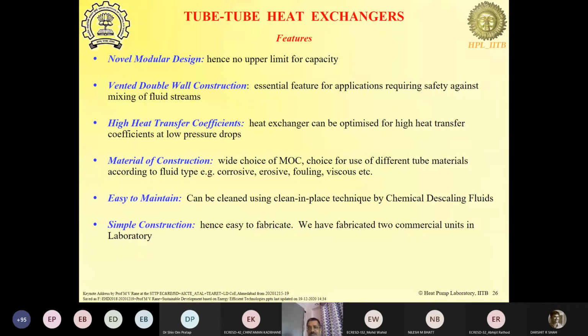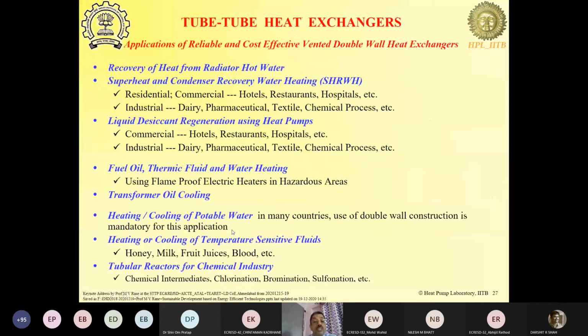So the cost of the heat exchanger can be much lower than the traditional alternatives, without compromising the compactness or safety or inventory of the heat exchangers. Then it is easy to maintain because you're just cleaning in place. You just circulate the cleaning fluid if there is any scaling or the like. It is simple to fabricate once you have the design programs. So we have deployed these for heat recovery from radiator hot water, and superheat recovery from condensers, in various residential, commercial, and industrial applications. Liquid desiccant can be regenerated using this, as I said, in a hybrid air conditioning system.